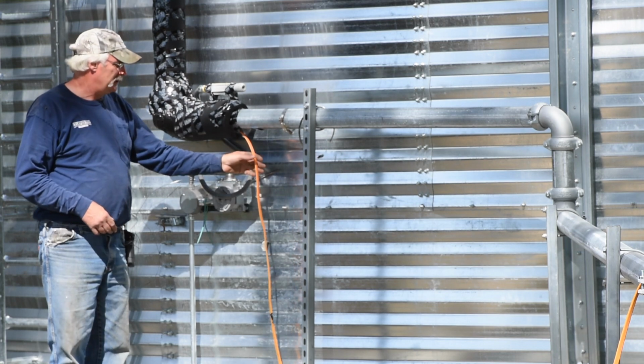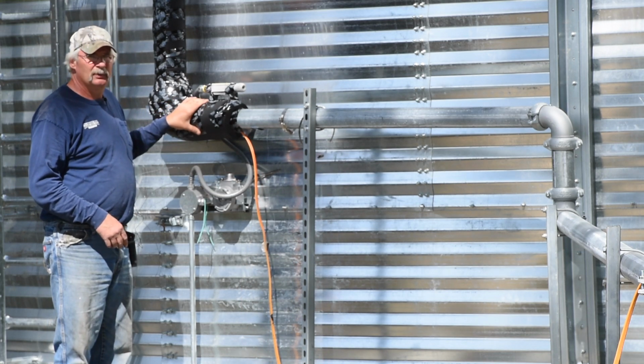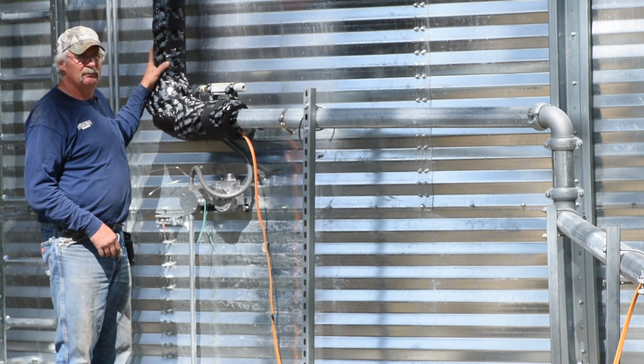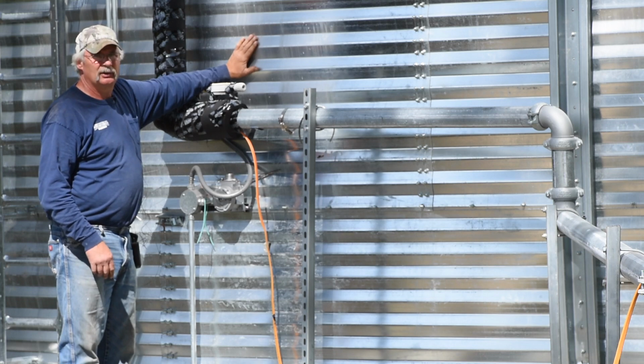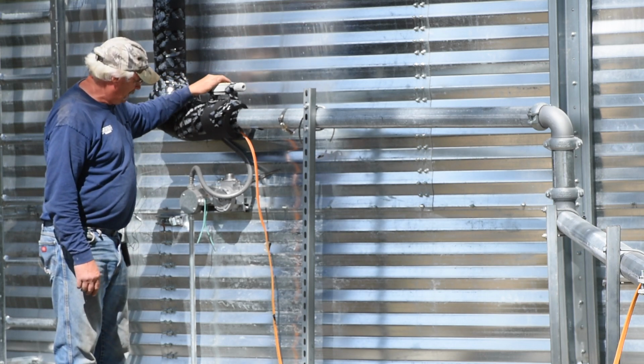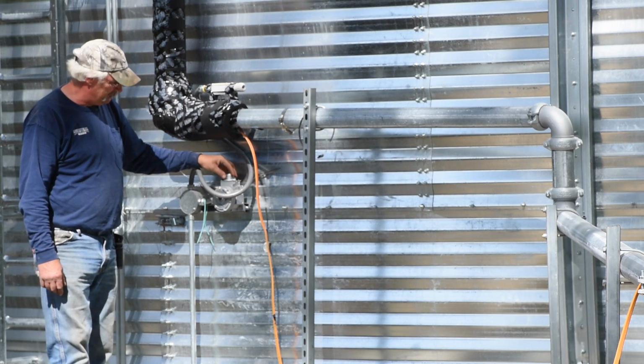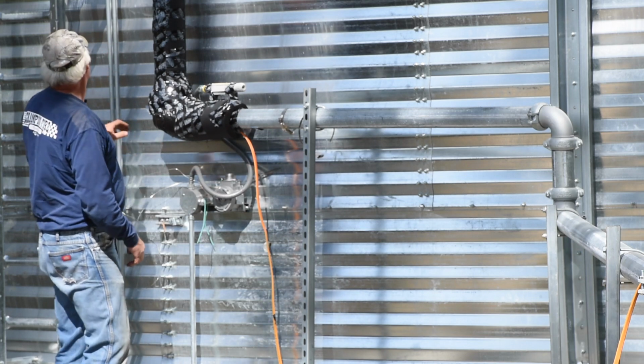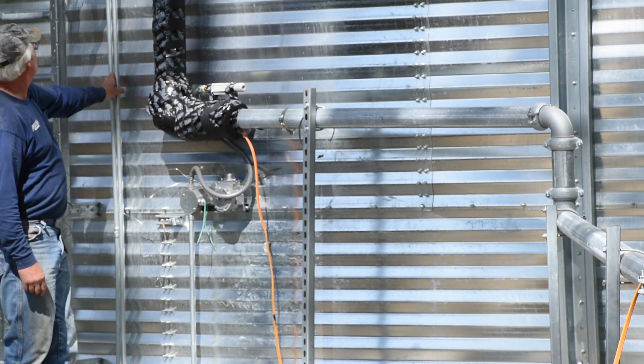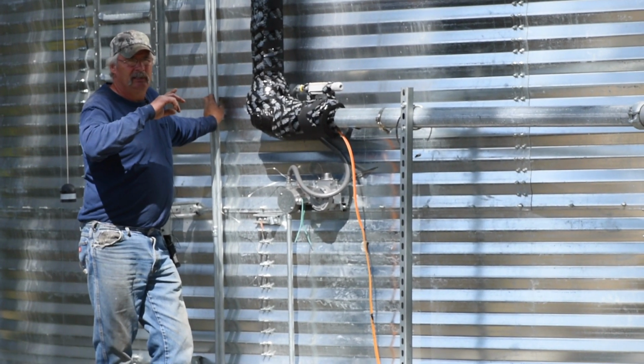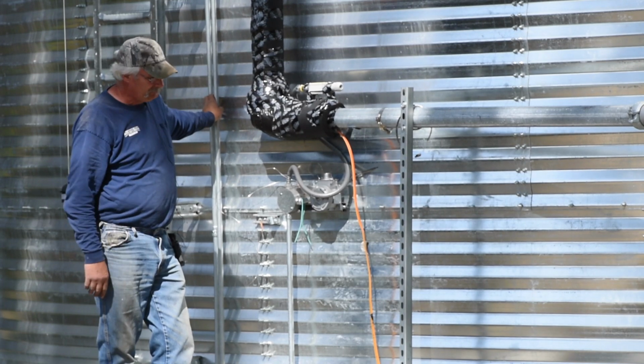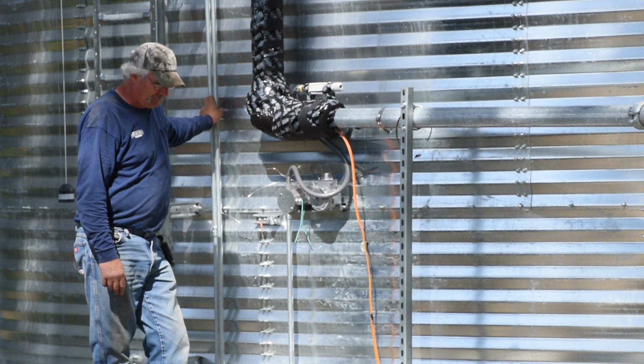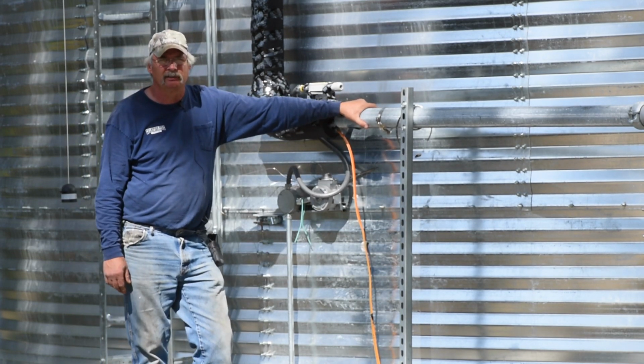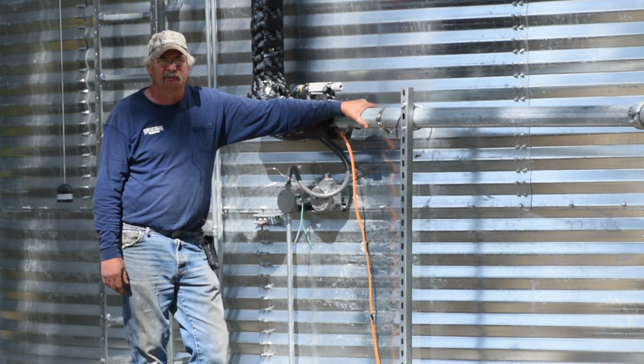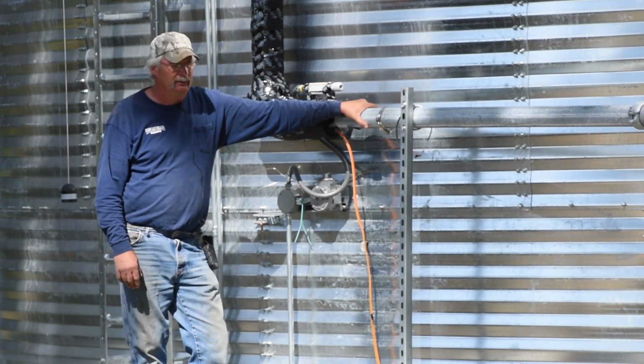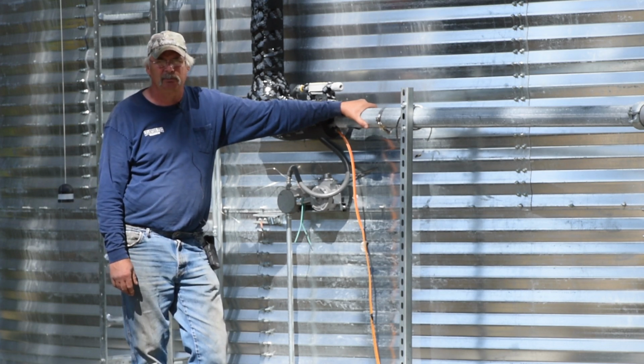We're in the process right now. There's heat tape going on, covering the pipe, and then this gets covered with a foil wrap. This is going to have an R value of 20 on the outside and coated. These are actually the probes here and the heat tapes that'll be tied back. These conduit lines going up here are for the heater and the high-low level alarm. Basically the heat pumps, circulating pumps, and heat exchangers will be inside the fire pump house. So right now they're in the process of working on this and finishing it up. This should be done within the next couple of weeks.